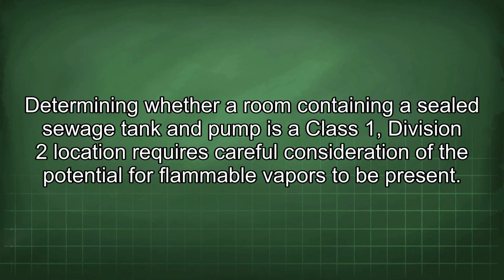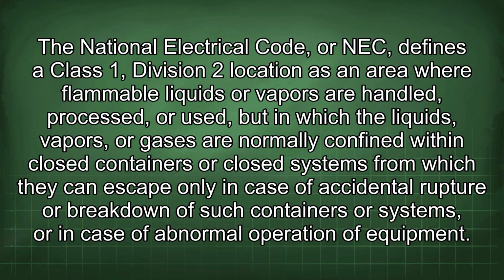Determining whether a room containing a sealed sewage tank and pump is a Class 1, Division 2 location requires careful consideration of the potential for flammable vapors to be present. The National Electrical Code, or NEC, defines a Class 1, Division 2 location as an area where flammable liquids or vapors are handled, processed, or used, but in which the liquids, vapors, or gases are normally confined within closed containers or closed systems from which they can escape only in case of accidental rupture or breakdown of such containers or systems, or in case of abnormal operation of equipment.